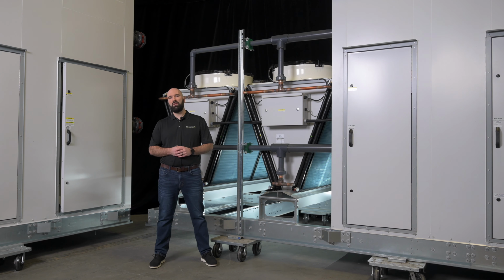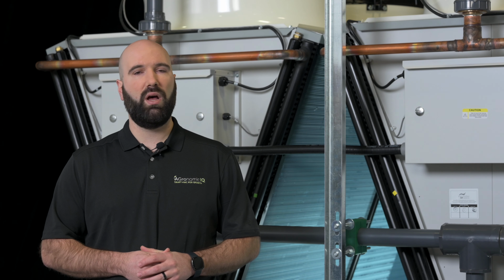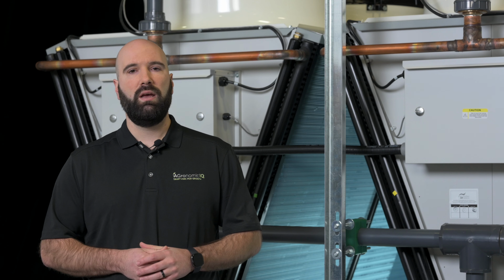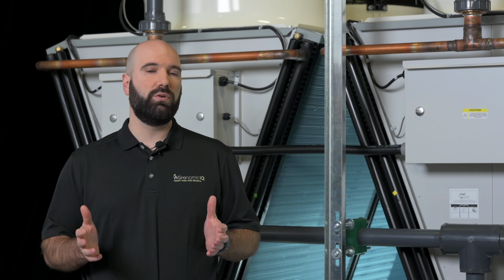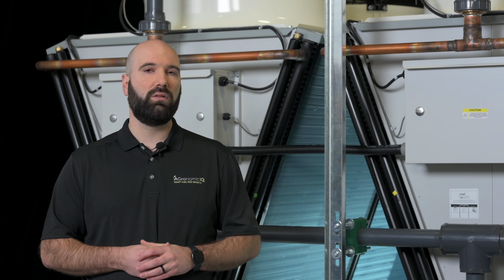These coils are Seacoast coated, so you'll see that blue coating behind me. That's a salt spray rated coating. So these can be appropriately applied anywhere in North America, whether you're right on the coast or you're more inland. And that provides a great corrosion protection for that coil, ensuring a long lifespan.